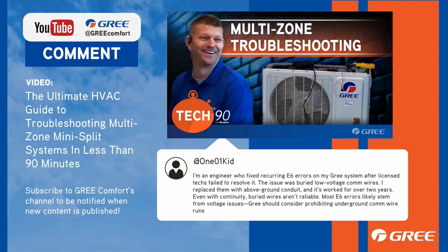I'm an engineer who fixed recurring E6 errors on my GREE system after licensed techs failed to resolve it. Well, that seems combative. The issue was buried low voltage comm wires. I replaced them with above ground conduit and it's worked for over 2 years. Even with continuity, buried wires aren't reliable. Most E6 errors likely stem from voltage issues. GREE should consider prohibiting underground comm wire runs.